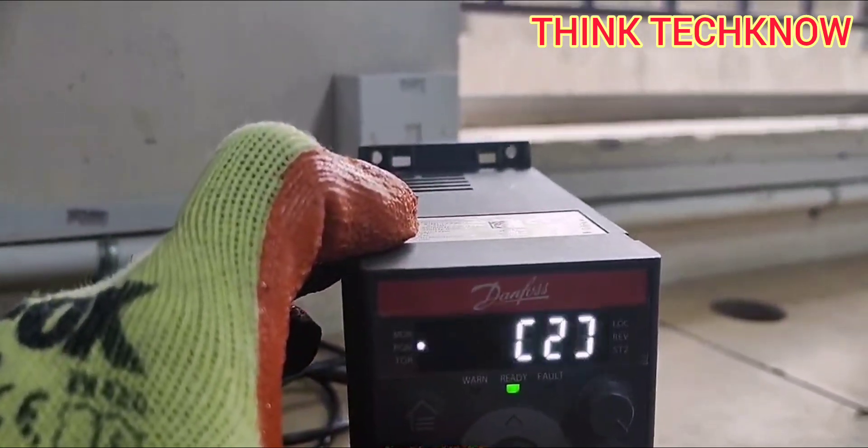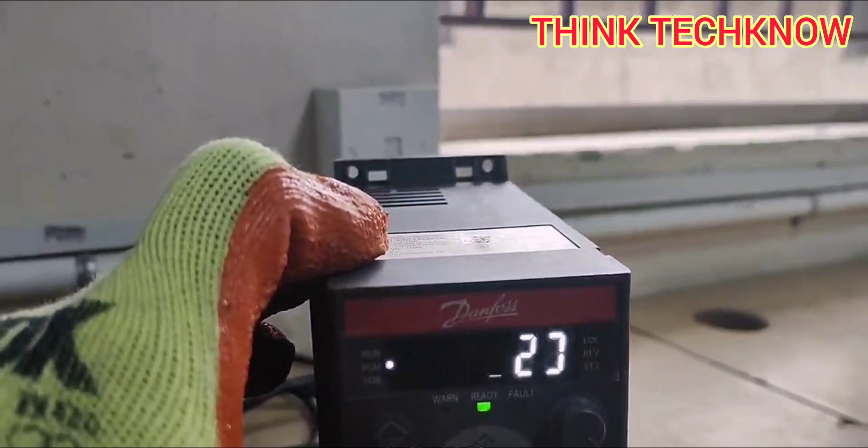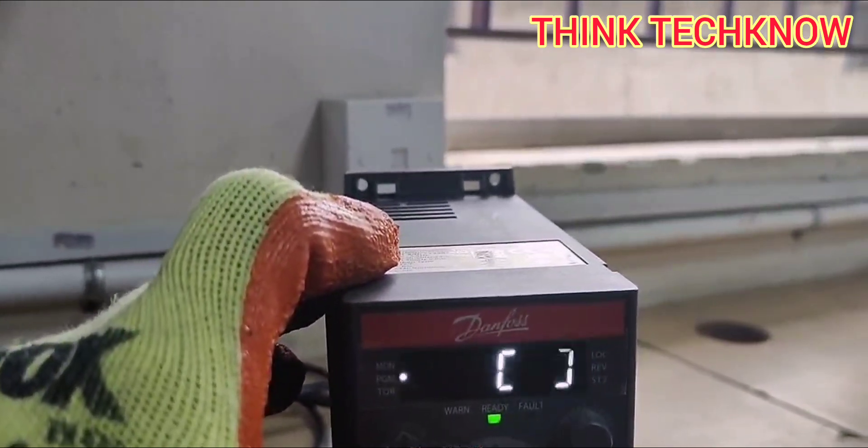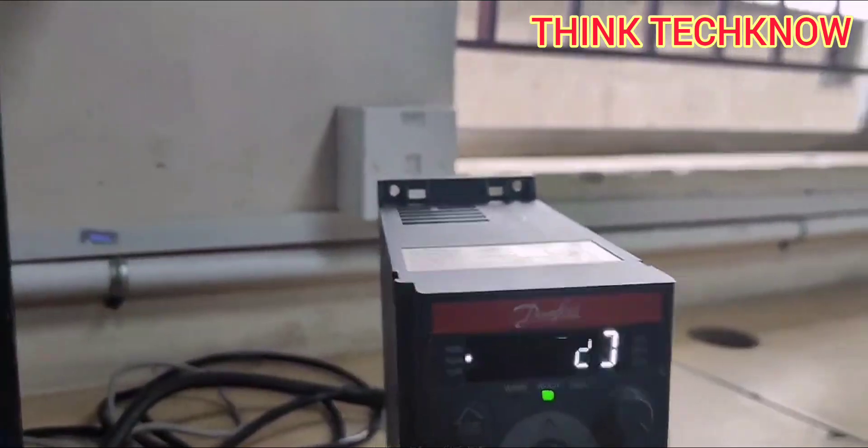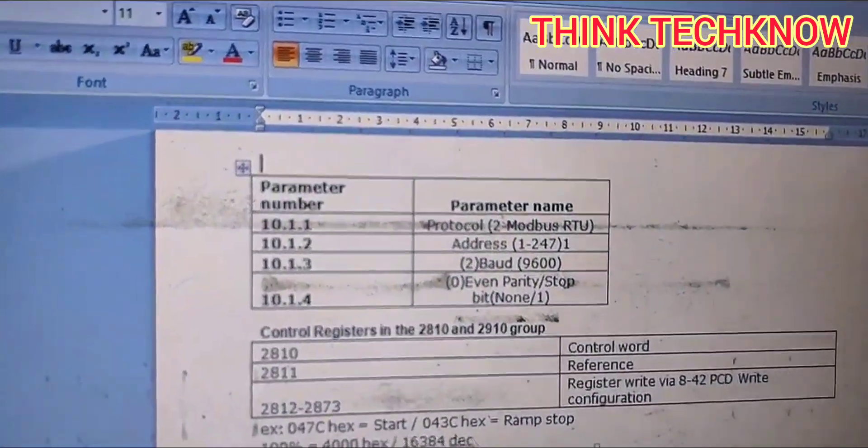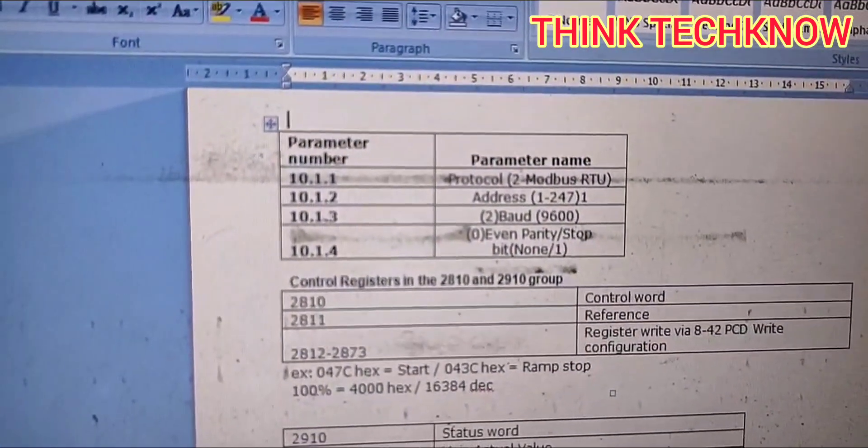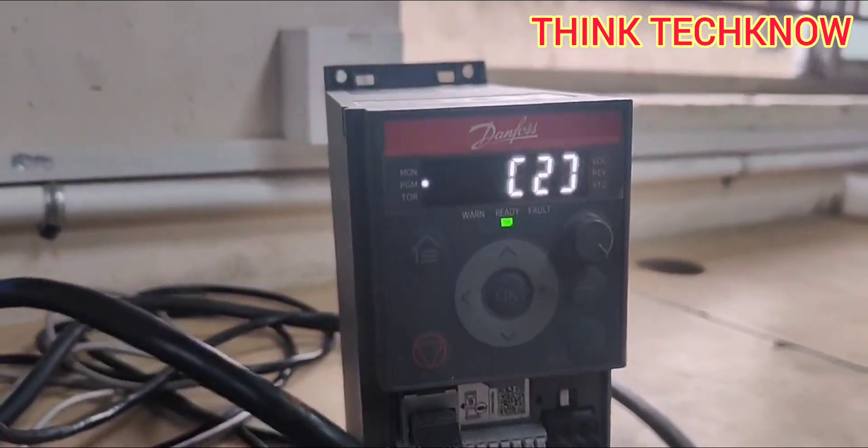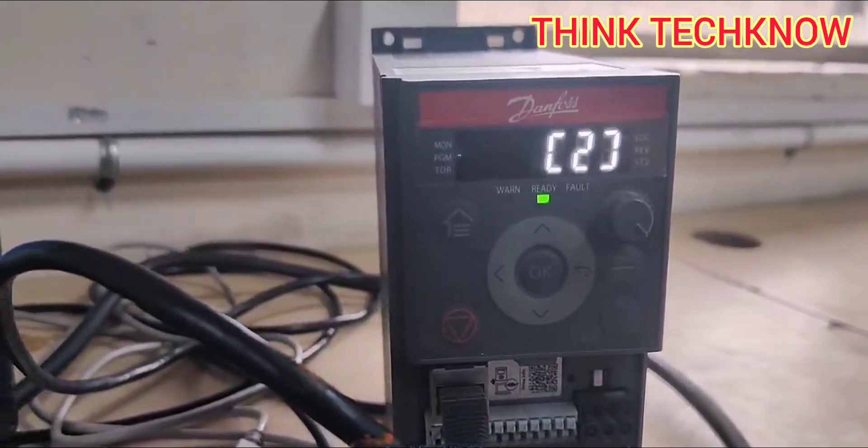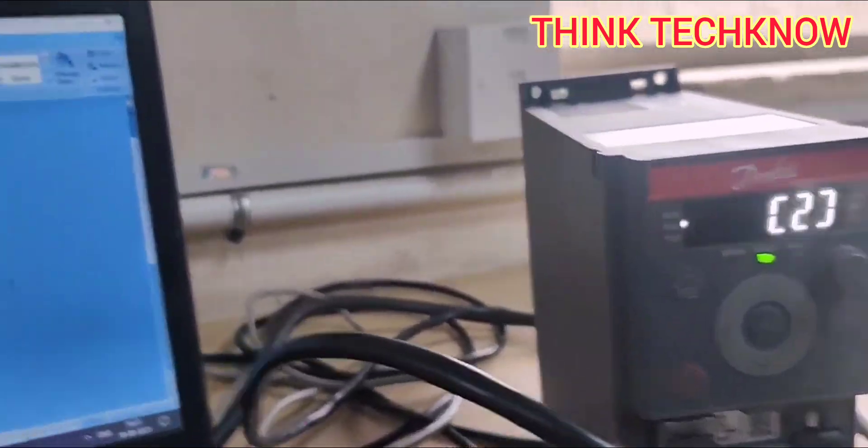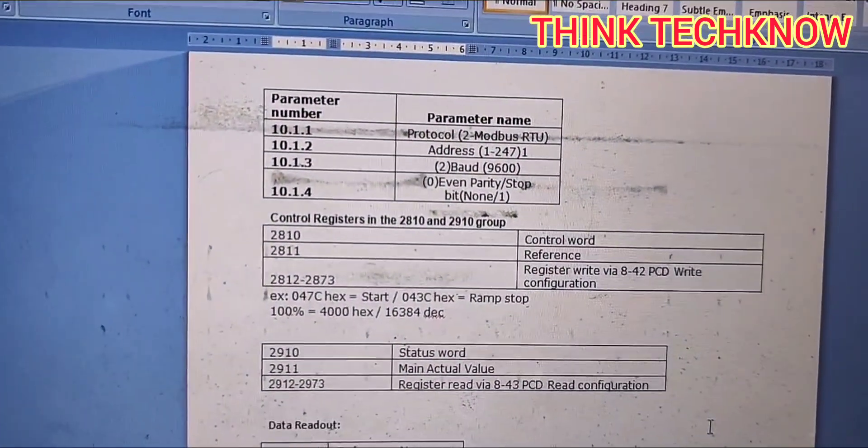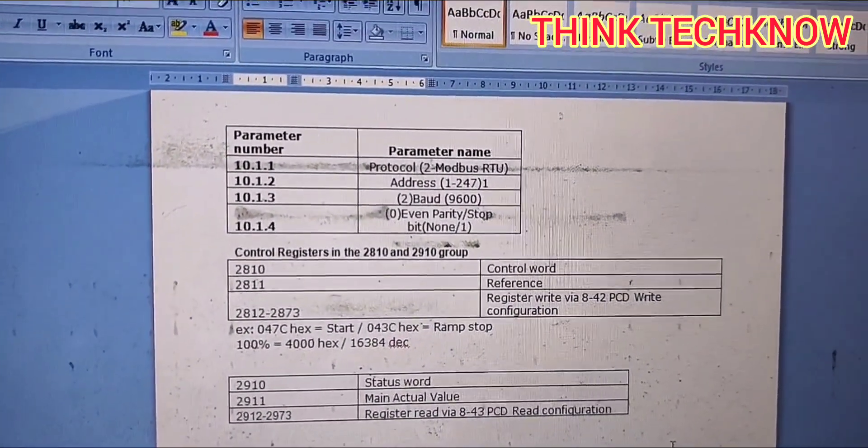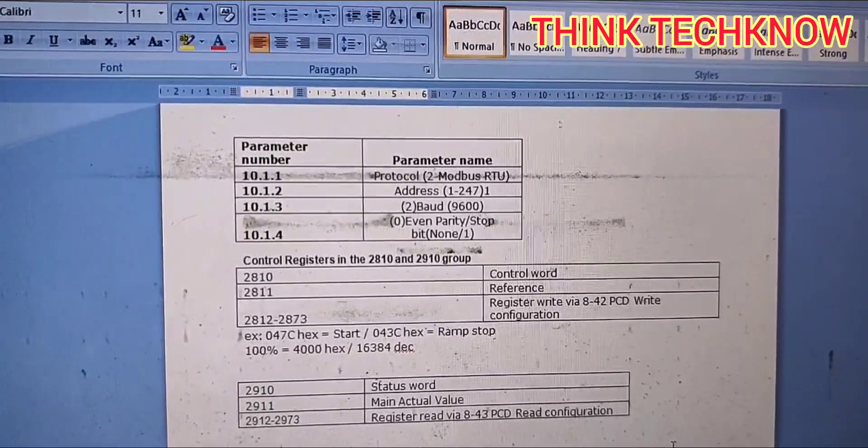For baud rate, you can fix number 2 for 9600, number 3 for 19200. You can see here on the screen: 2 for 9600 and 3 for 19200. This is the standard communication protocol condition.